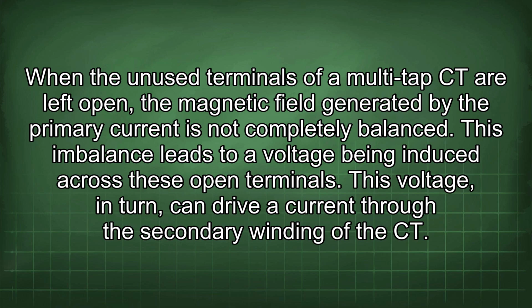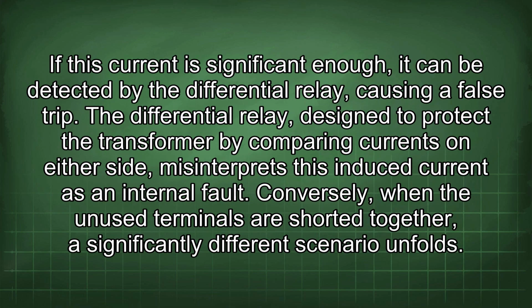This voltage, in turn, can drive a current through the secondary winding of the CT. If this current is significant enough, it can be detected by the differential relay, causing a false trip. The differential relay, designed to protect the transformer by comparing currents on either side, misinterprets this induced current as an internal fault. Conversely, when the unused terminals are shorted together, a significantly different scenario unfolds.